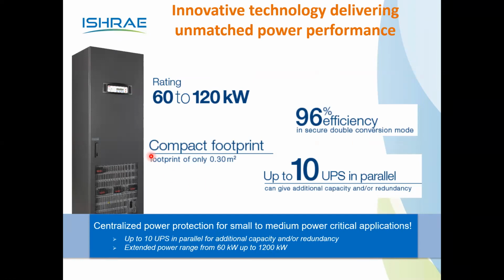The picture is showing 60 to 120 kilowatt. When it comes to kilowatt, the efficiency of this technology is better. The power loss, the heat loss, is very low. It is 96% efficiency with a compact footprint. Even transformers may not be required for this kind of unity output power factor UPS system, because it has an inbuilt technology of EDCP, the electronic DC protection filter, inside. There is no need of a transformer. So without a transformer, there are technologies available that can give better performance and better efficiency.